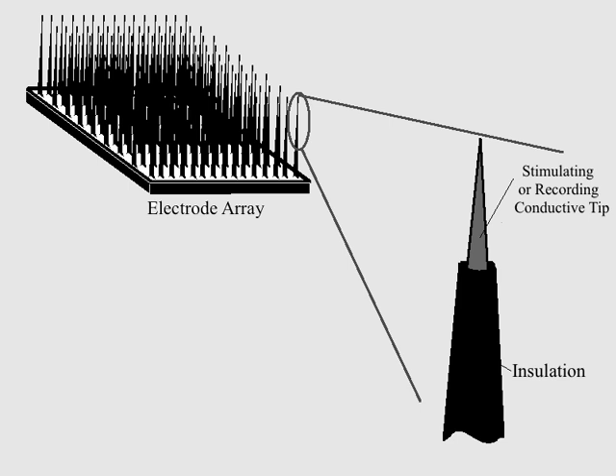The voltage required for stimulation may change significantly over the life of a single electrode. This change is required to maintain a consistent current output through variations in the surrounding environmental resistance. The changes in resistance may be due to adsorption of material onto the electrode, corrosion of the electrode, encapsulation of the electrode in fibrous tissue known as a glial scar, or changes in the chemical environment around the electrode.